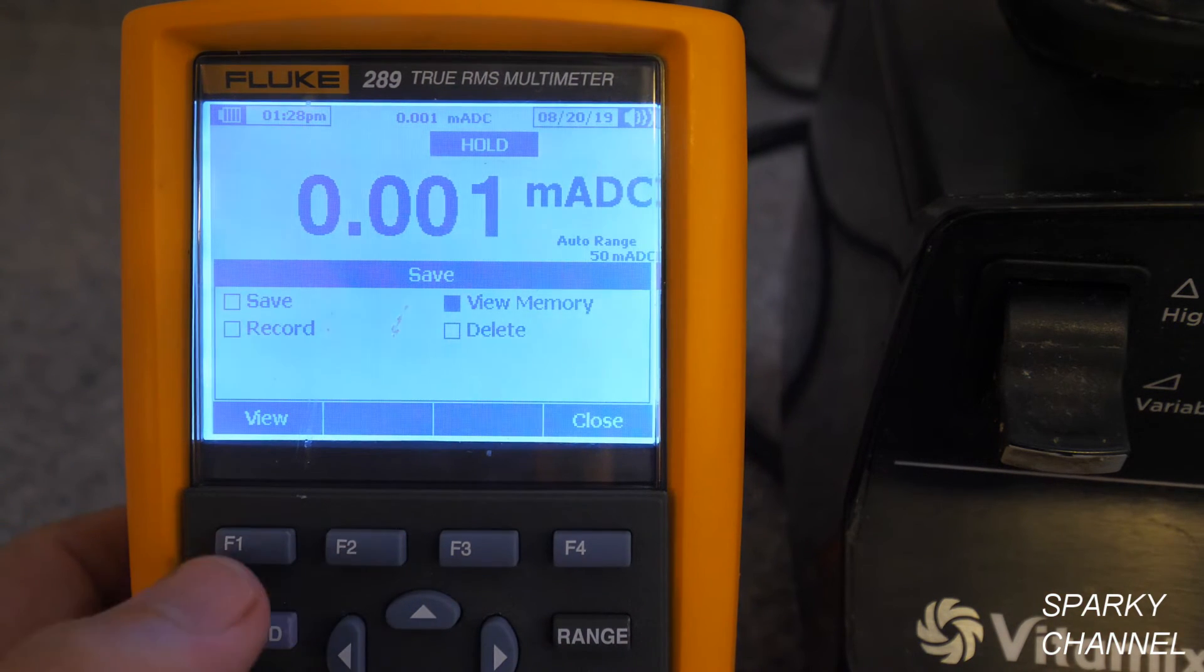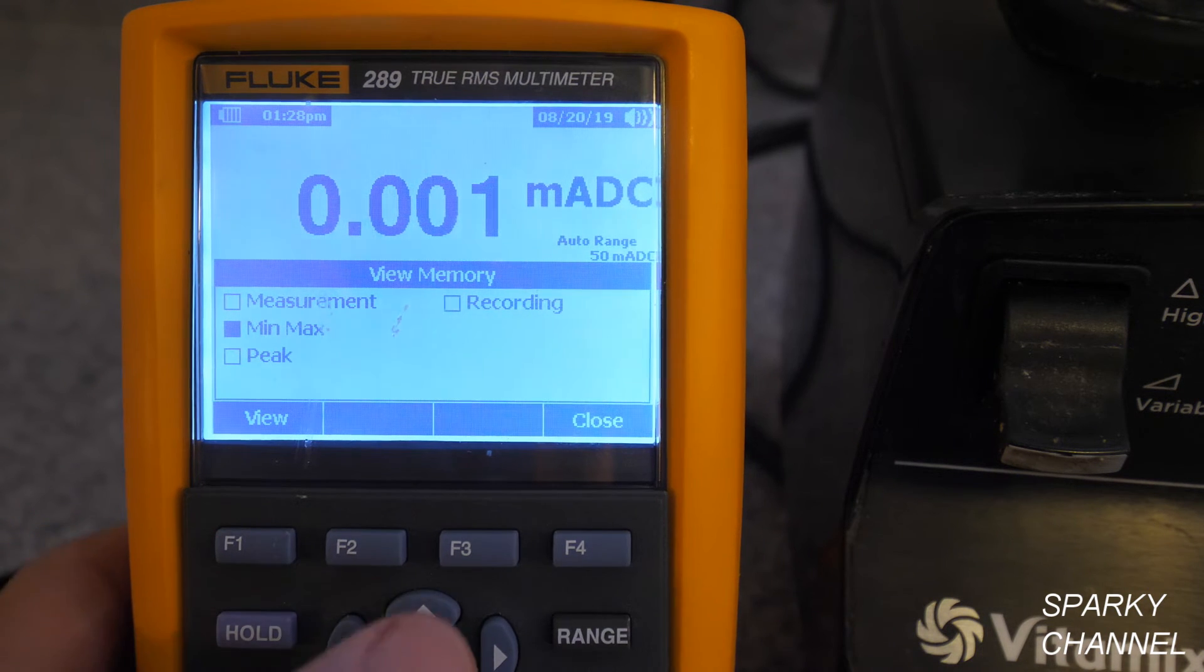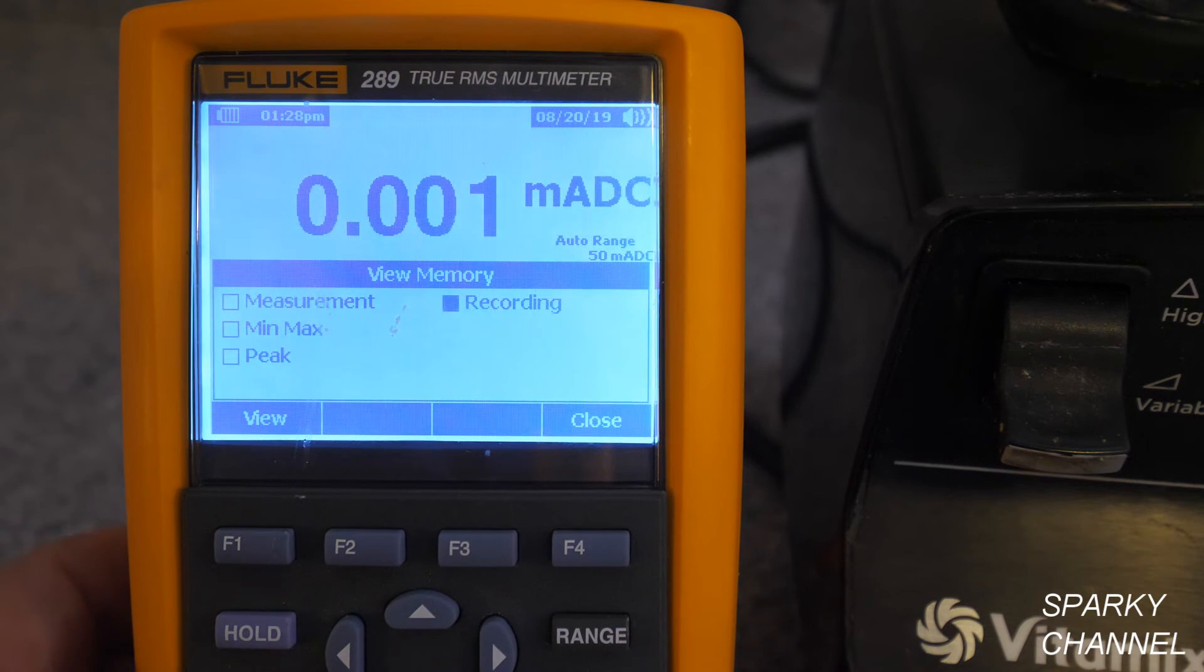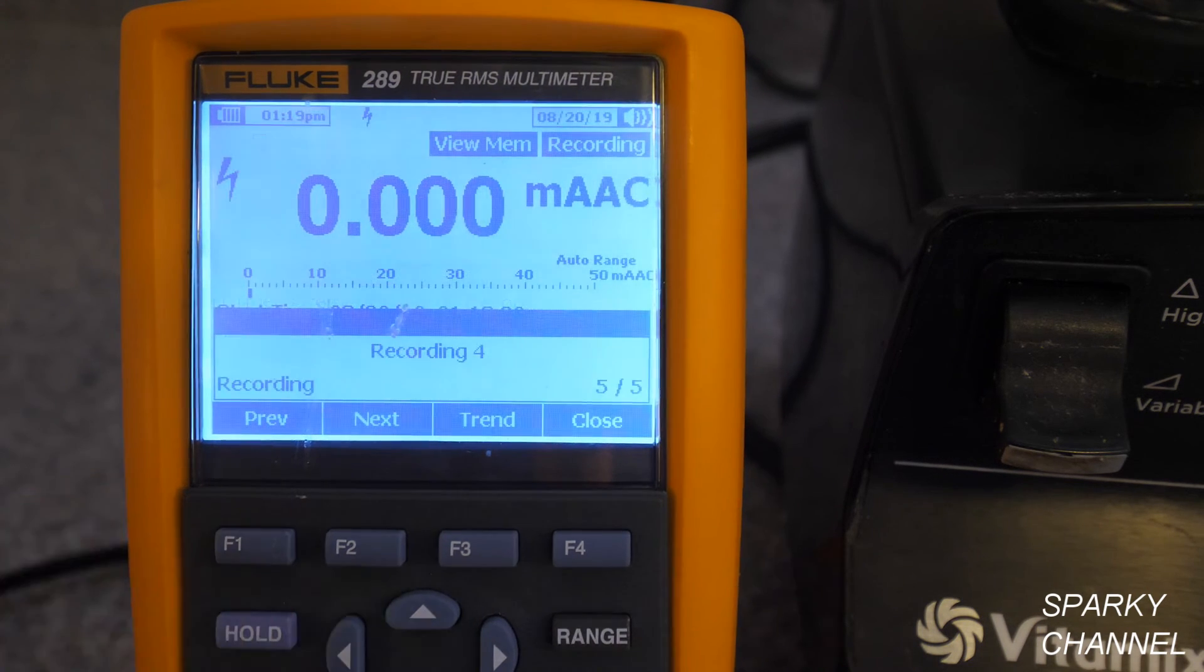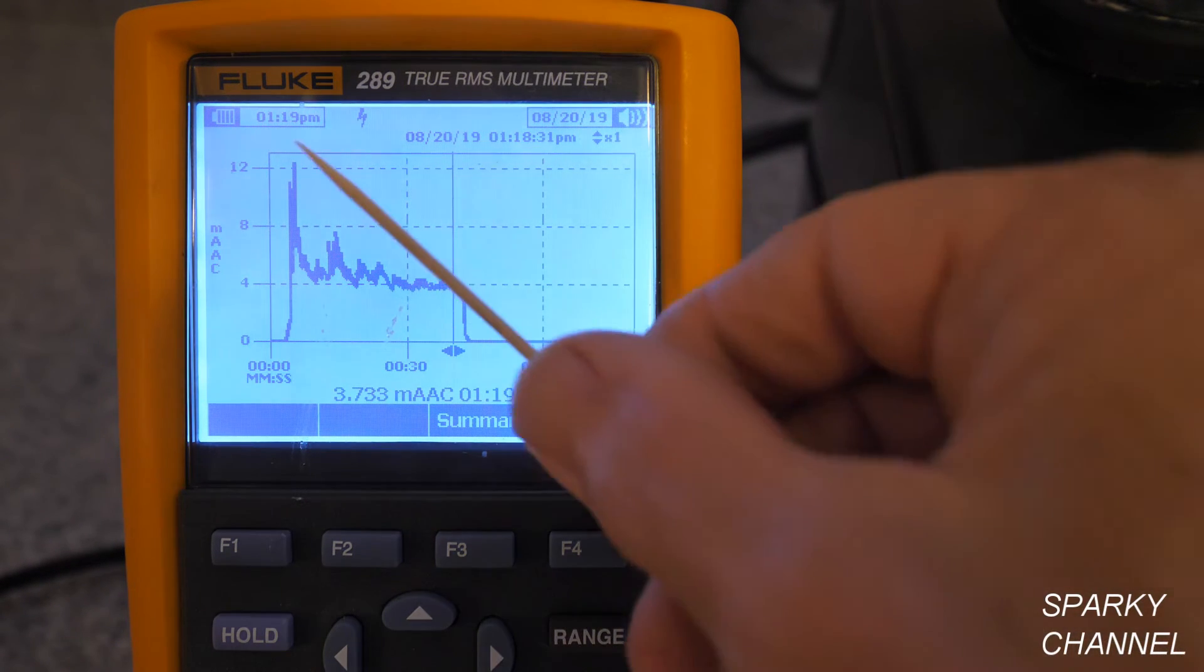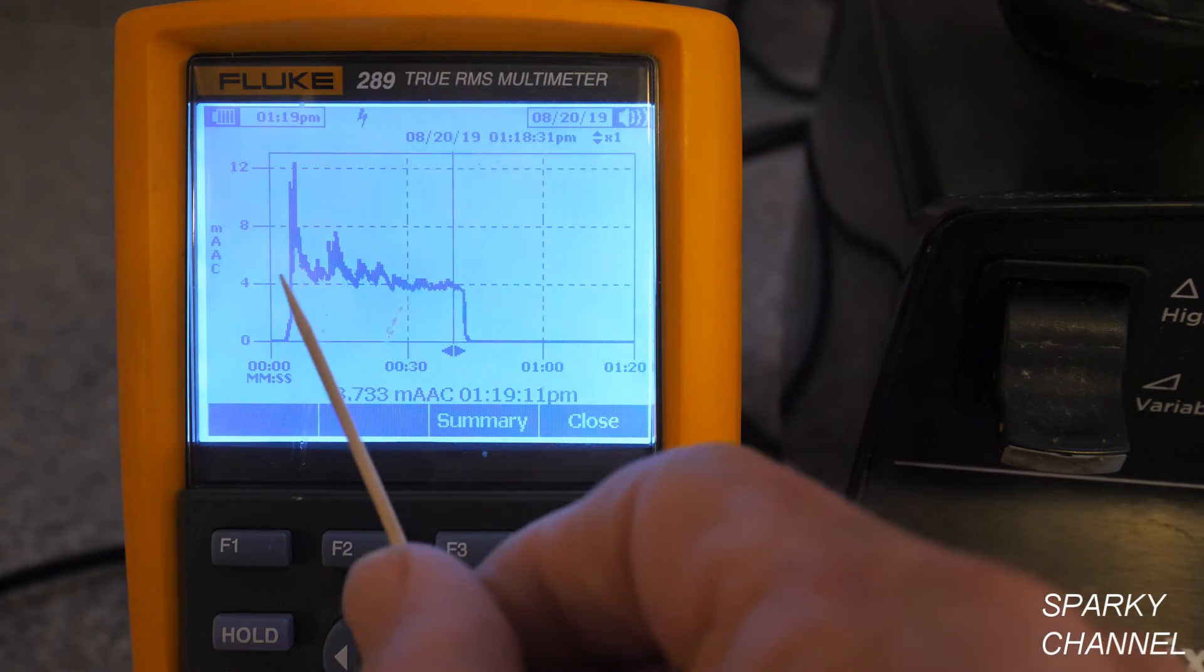I'm going to save. View memory. And I go up to measurement. And over to recording. And say view. And say trend. And there's our graph again. So this actually got up over 13 amps. Pretty amazing. And the average was 4.5. That looks about right.